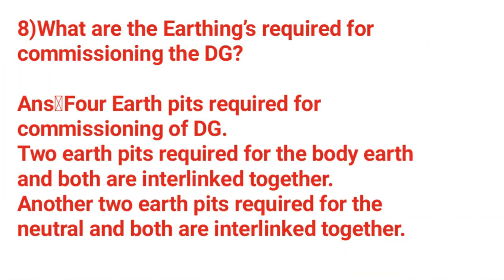What are the earthings required for commissioning a DG set? Four earthings are required for commissioning a DG set: 2 earthings for body earthing and 2 earthings for neutral earthing. Both body and neutral earthings are interlinked together.